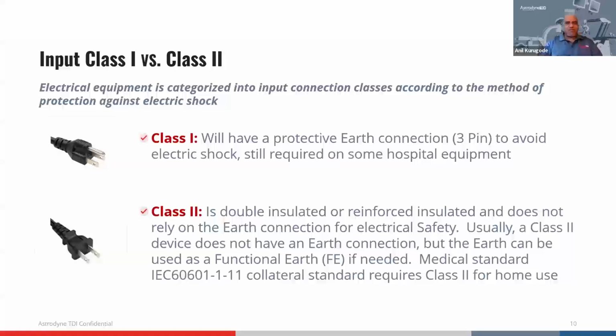Very simply speaking, if there's an earth available in the AC wall outlet, and the equipment is tied to that earth, you should consider yourself safer, or less at risk, because the patient who can accidentally touch the equipment is not exposed to any hazardous voltage. So Class I automatically involves a three-prong plug where the middle prong is the earth.